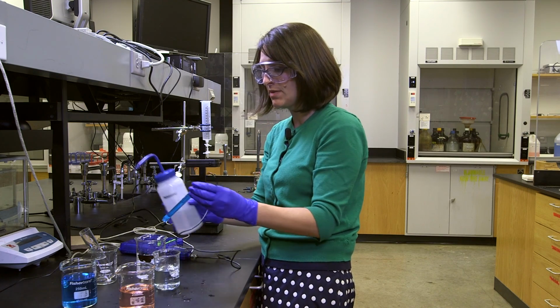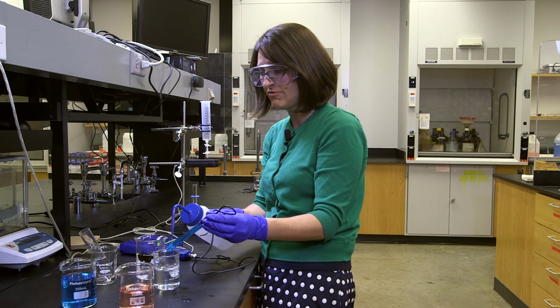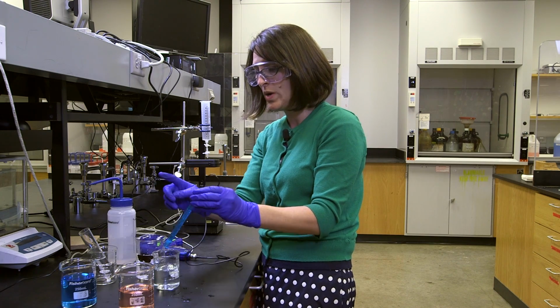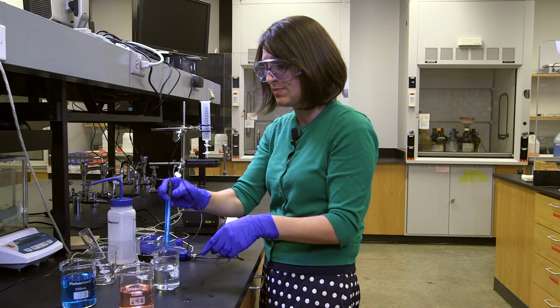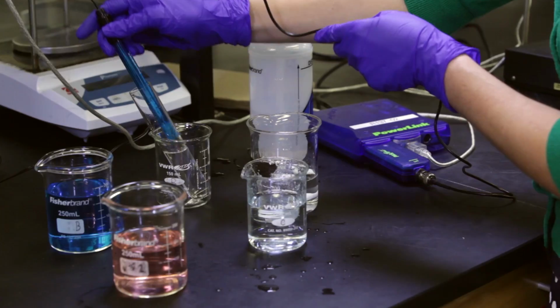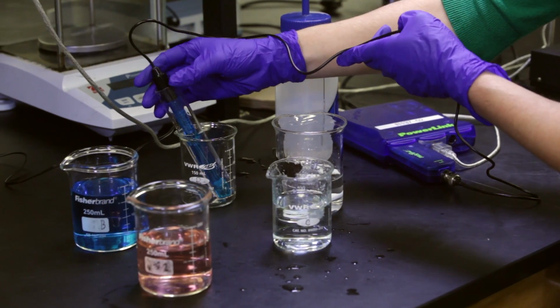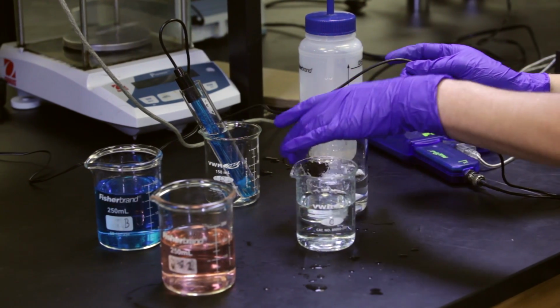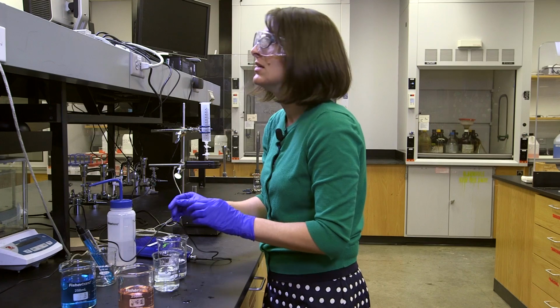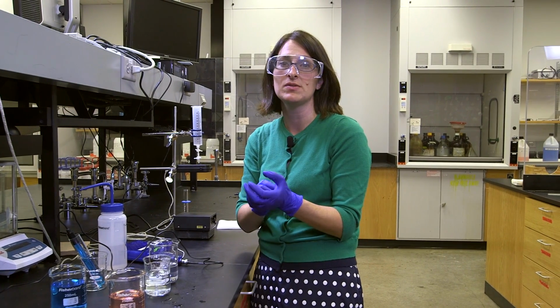Every time you're recording a pH, you need to stop and rinse off your pH probe in between. When it's not in use, it needs to be back in its storage solution. Do not lay these on the counter. They have to be in liquid at all times. So pretty easy to use. That's how you use a pH probe.